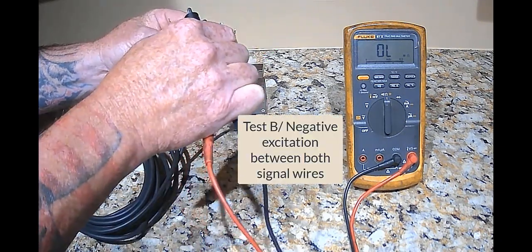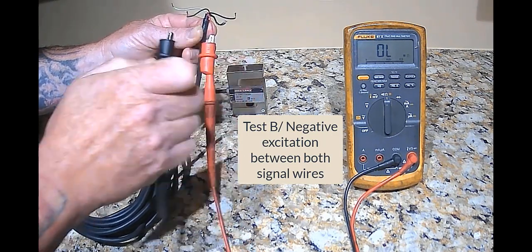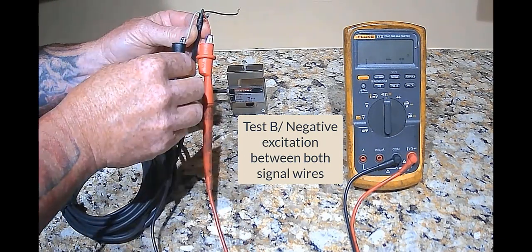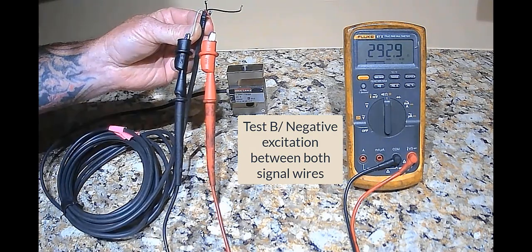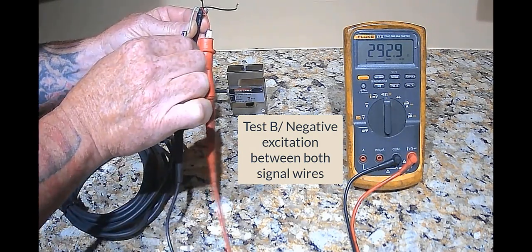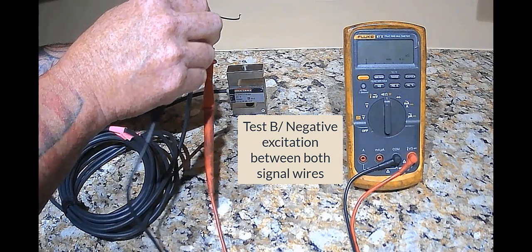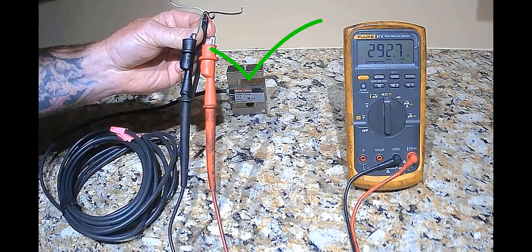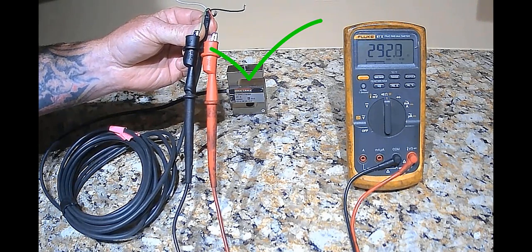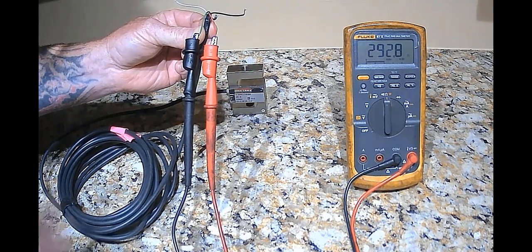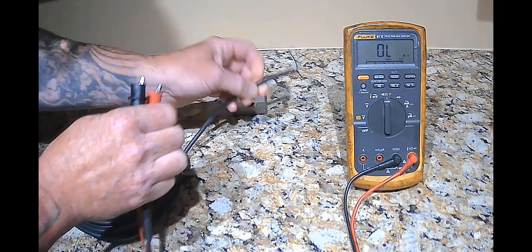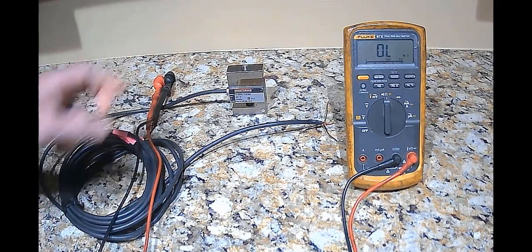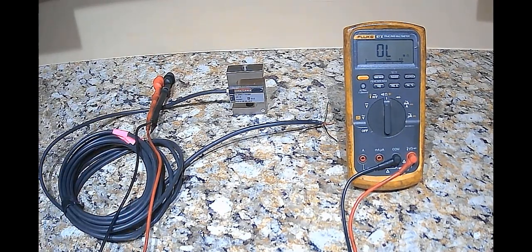Test B is negative excitation to negative signal. Then negative excitation to positive signal. These two readings should match within 1 ohm. The two A readings must match and the two B readings must match, but A does not have to match B. If errors are found, chances are there is a broken or shorted wire that could have been caused by a shock load, vibration, wear, or temperature extremes.